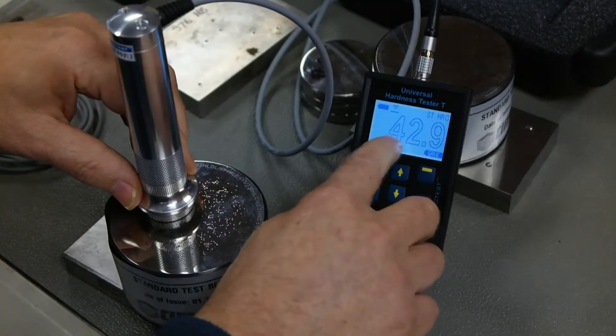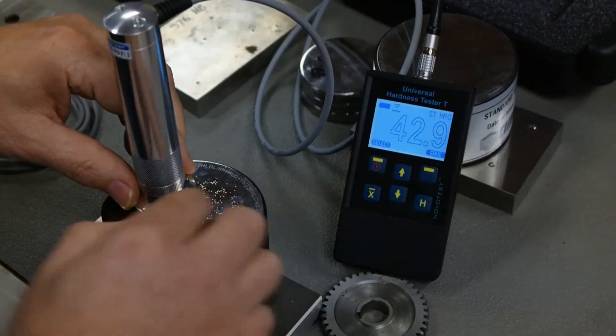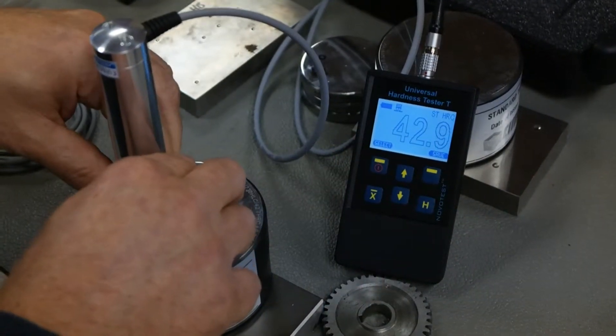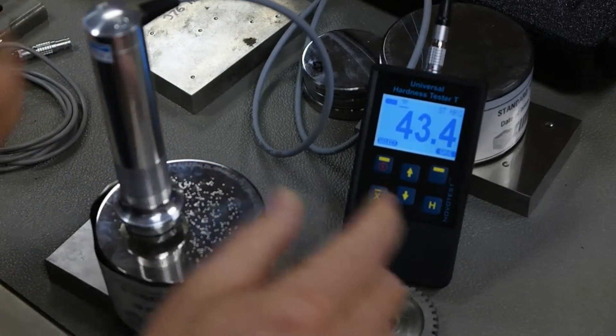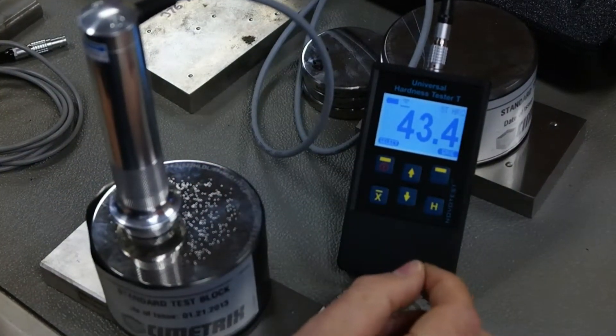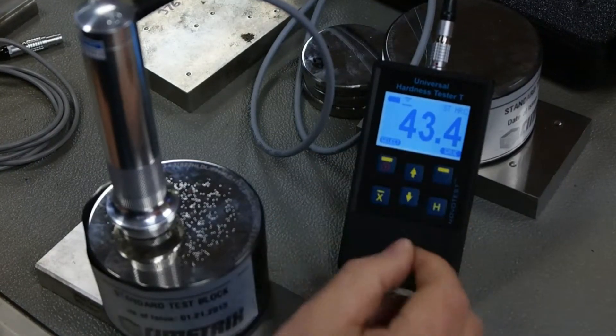So it's going to show here not a solid display, just showing the border. So there's 42.9, 43.4. And it says that because those tests were all within tolerance, it's now showing the average of the result.